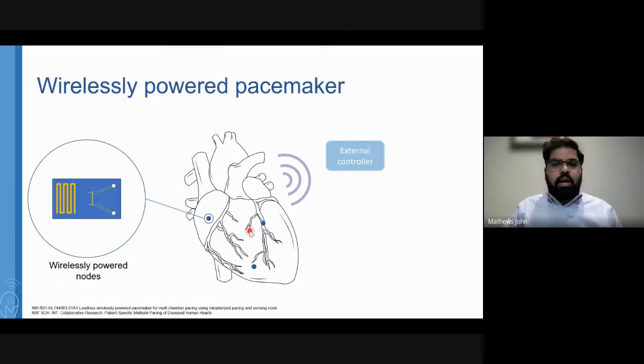Let's assume there are different nodes in the atrium, the left ventricle, and the right ventricle. These nodes communicate with an external controller via wireless transmission, which includes communication and wireless power transfer. Once that communication is done, the controller says go ahead and pace with this specific frequency, these delays, and this specific pulse width, prompting the devices to stimulate at those specific locations based on what the controller is saying.